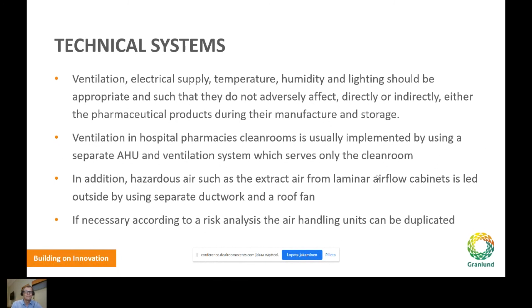Ventilation is normally implemented by using a separate air handling unit and ventilation system which serves only the clean room area. And in hazardous air, if we have BSL 2 or 3, then the extract air from laminar airflow cabinets is let outside by using separate ductwork and a roof fan. And if necessary, according to risk analysis, the air handling units can be duplicated so that one is operating and one is reserve. If there is maintenance or a failure in the unit, then it changes automatically to the reserve system. Pipes and drains should be easy to clean.